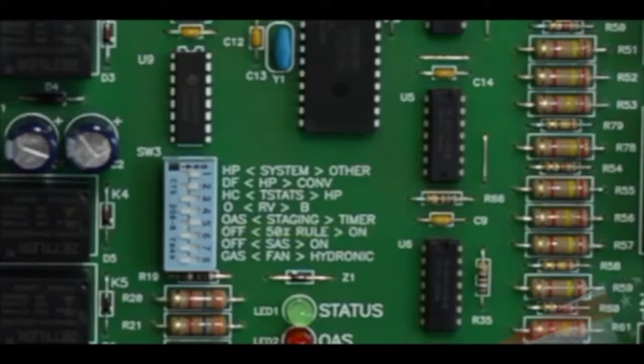Dip switch number 6, the 50% rule, is a unique feature allowing you to inhibit second stage from calling if you don't have enough zones calling. If you have less than 50% of the zones available calling, second stage will not be energized. This allows the BMPlus to truly stage to capacity demand. If only 1 zone calls out of 3, you have the bypass to divert the capacity from the unused zones to the used zones to maximize the efficiency of BTUs produced.